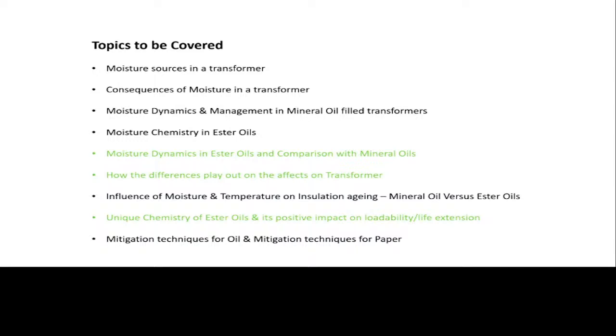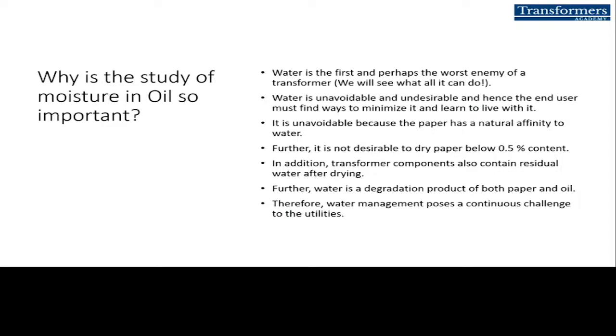The topics I'm going to cover are the following: moisture sources in transformers, and most importantly, moisture dynamics in ester oils compared with mineral oils, and how these differences play out as effects on the transformer. I'll also cover the influence of moisture and temperature on insulation aging, again comparing mineral oil and ester oil, with some explanation based on the unique chemistry of ester oils and its positive impact on loadability and life extension. Towards the end, I'll try to cover mitigation techniques for oil and for paper.